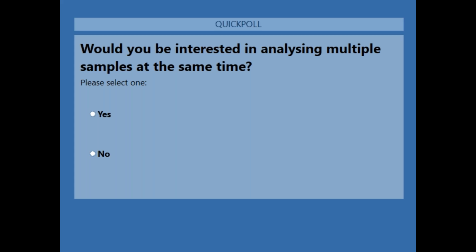samples like powder or polymer, but the difference is DVS is very suitable to control the high humidity sample, the high humidity, and we can go up to 98% relative humidity. So we can measure the porous material like zeolite or silicas.